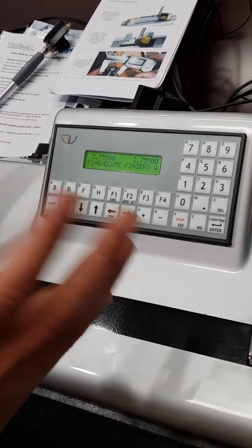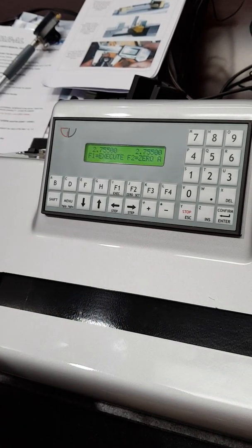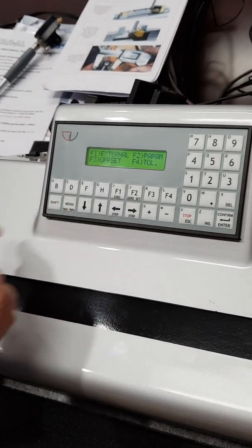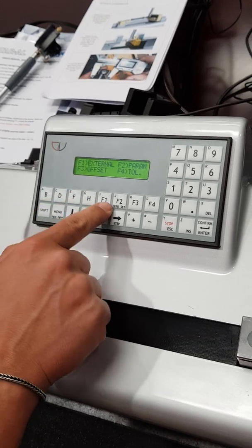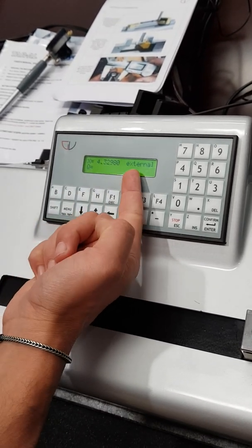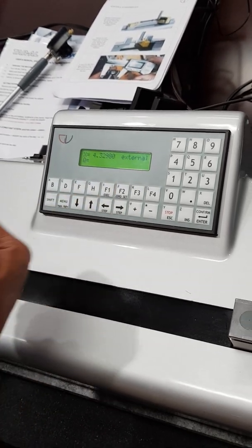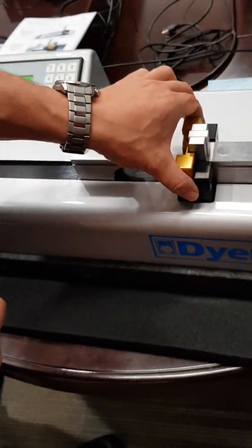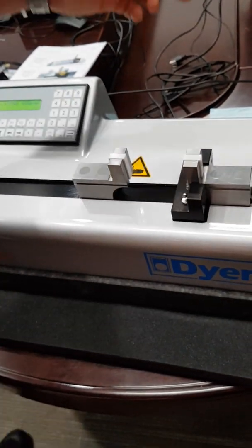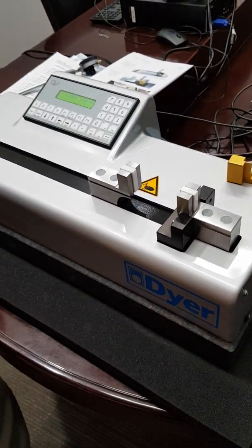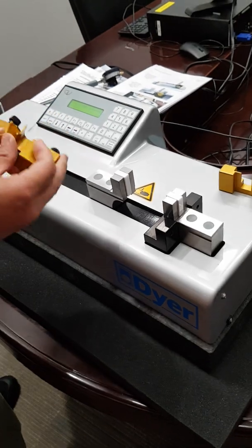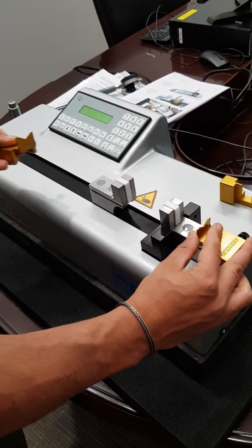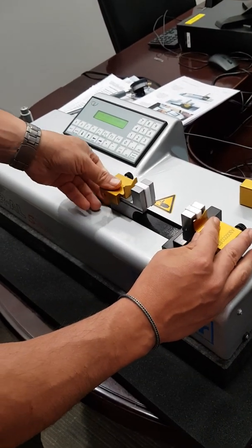Let's assume now we have to set an external instrument. We press menu and we select F1 for external and the machine is now working with external values. We remove the adapter for the bore gauge and we locate the one for the external micrometer.